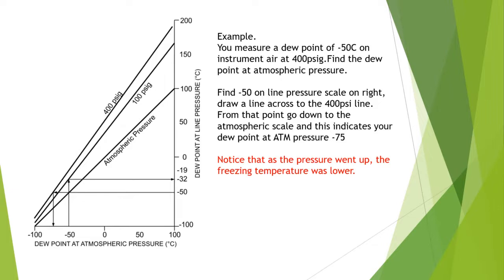The example in the ILM: measuring a dew point of -50°C on instrument air at 400 PSI — find that on the pressure scale and trace to the corresponding atmospheric dew point, approximately -75°C. Comparing at 100 PSI shows a different result, demonstrating that as pressure goes up, the freezing temperature is lower. The conversion chart and detailed math are described very well in the ILM.